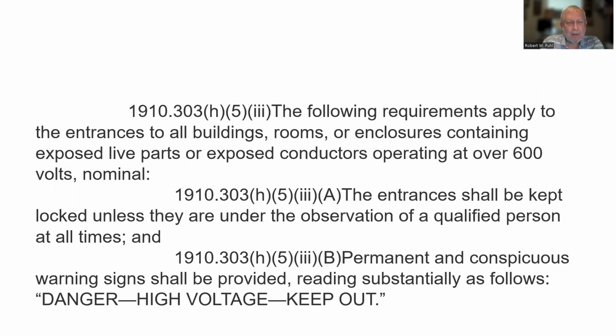The following requirements apply to the entrances of all buildings, rooms, or enclosures containing exposed live parts or exposed conductors operating at over 600 volts. The entrances shall be kept locked unless they are under the observation of a qualified person at all times, and permanent and conspicuous warning signs shall be provided, reading substantially as follows: danger, high voltage, keep out.